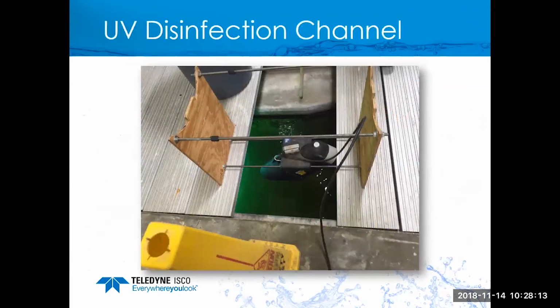So here's a UV disinfection channel, and this is another one that's becoming more and more popular. People want to measure this, and in the past, the way they do it is you have a moving weir gate at the end, and you try to assume some flows based on the gate position. But now we're finding more and more people want more accuracy in that so they can dose or pace their lights correctly, and the laser now is used in some of these channels.